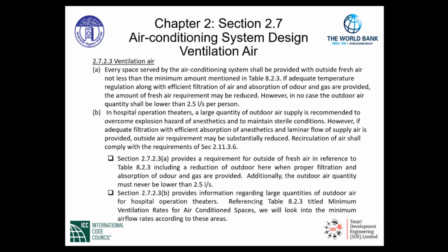Now, just to summarize, section 2.7.2.3a provides a requirement for outside of fresh air in reference to table 8.2.3, including a reduction of outdoor air where proper filtration and absorption of odor and gas are provided. So we could provide a reduction of outdoor air. Additionally, the outdoor air quantity, again, must never be lower than 2.5 liters per second. Last, section 2.7.2.3b provides very specific information and requirements regarding hospital operation theaters.